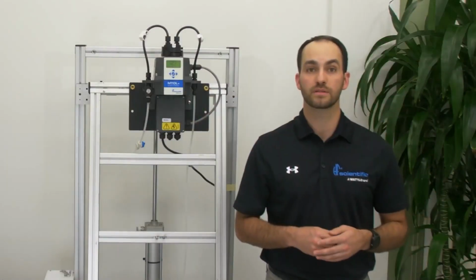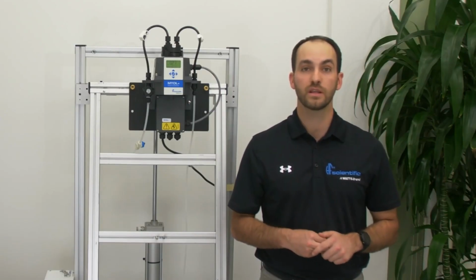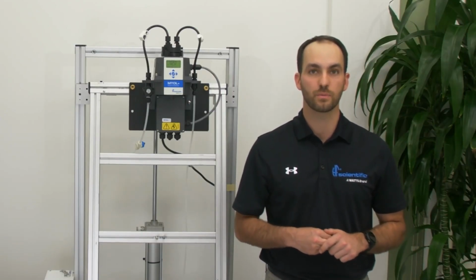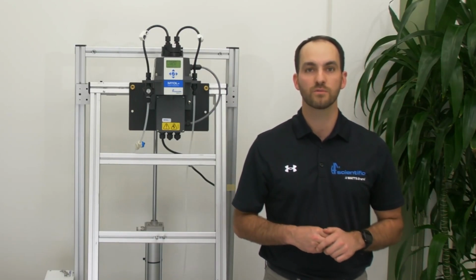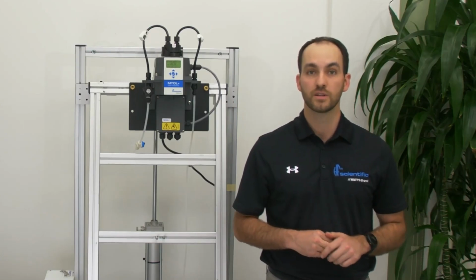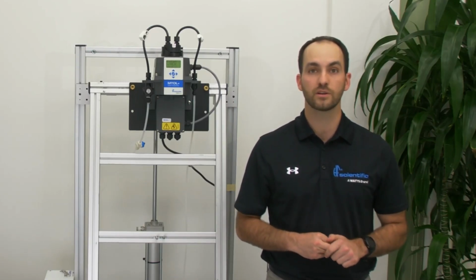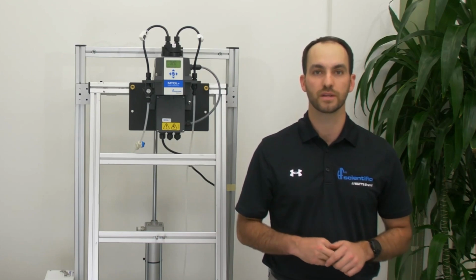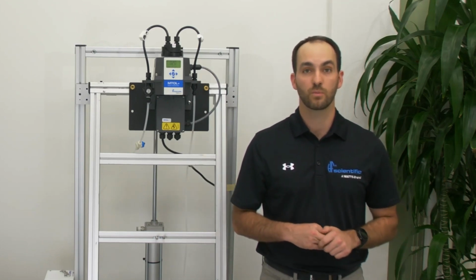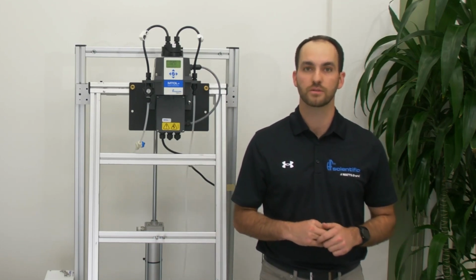The flow requirements for the analyzer are 100 milliliters a minute to 1000 milliliters per minute, but I have found the analyzer performs best at the lower end of this range, so I try to set the flow at 100 milliliters per minute to 200 milliliters per minute. This can be easily measured with a graduated cylinder and a stopwatch.